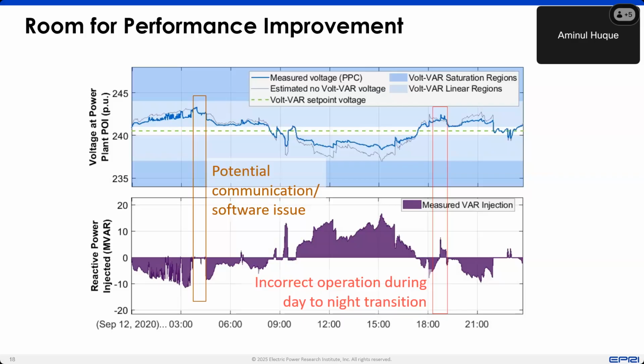But what we have seen during this project period are some incidents of communication issues, whether the inverter is not responding to the power plant controller or the power plant controller is not functioning properly. I'm showing one example of that around 4 a.m. It was not communicating for a certain time.